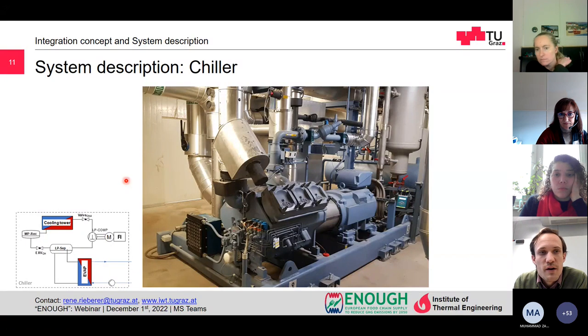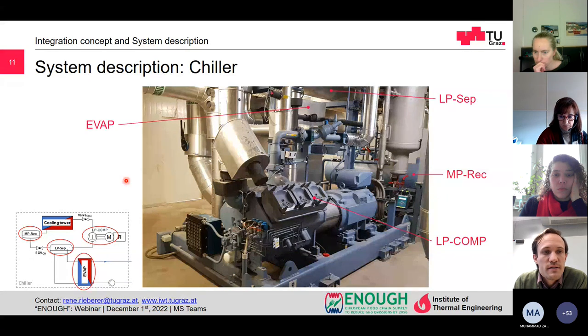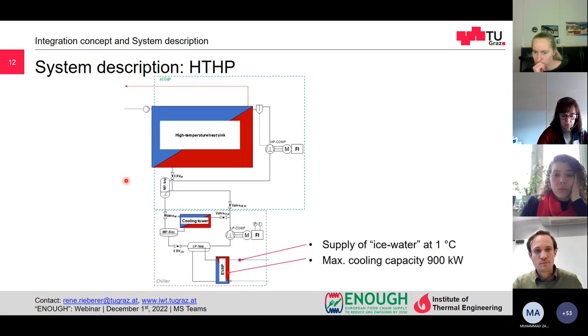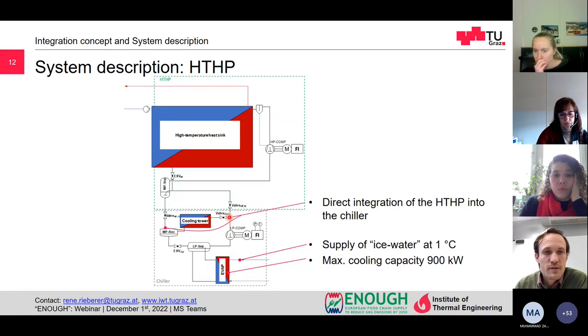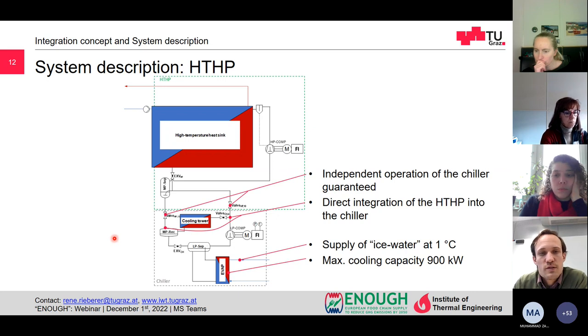So you can get a little bit of an imagination of the system. You can see a picture of our chiller. You can see the low pressure compressor, the medium pressure receiver, the low pressure separator, and the insulated evaporator. And into this chiller, the high temperature heat pump has been integrated, as already shown in the simplified scheme before. Here after the low pressure compressor and here before the medium pressure receiver, the high temperature heat pump was directly integrated, and there were also two valves integrated to guarantee an independent operation of the chiller, because the chiller is operated 24/7 and the high temperature heat pump is operated on demand.